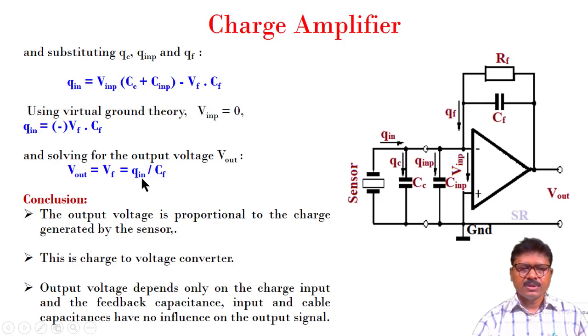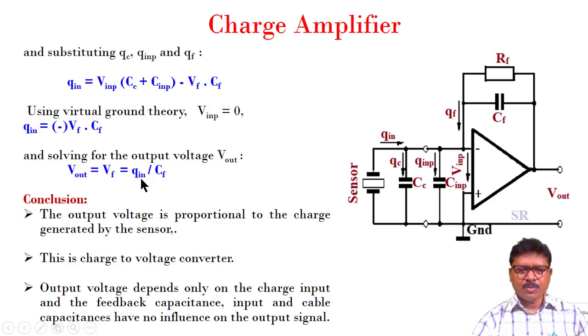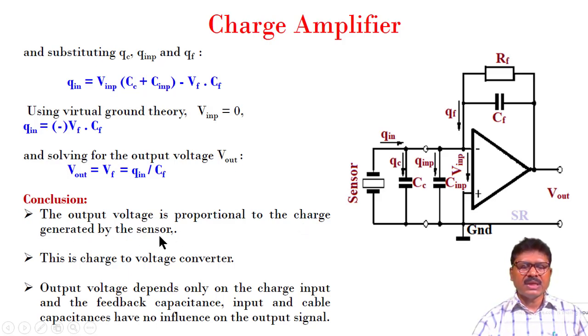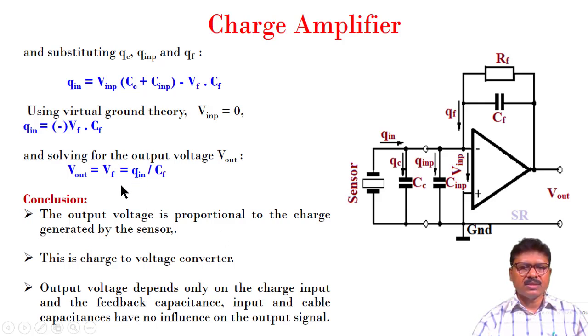The output voltage is proportional to the charge generated by the sensor. This is a charge-to-voltage converter because the output is voltage and the input is charge. Output voltage depends only on the charge input QIN and the feedback capacitance CF. Input and cable capacitance have no influence on the output signal.